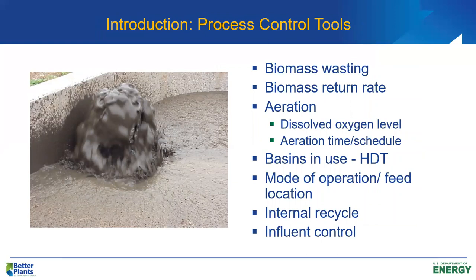In terms of process control tools, our primary tools are the biomass wasting rate (WAS) and the biomass return rate (RAS). Aeration is another key tool — how much aeration we're providing in the basin. The aeration system usually accounts for about 50% to 60% of our overall energy use, so we want to use it wisely to minimize operating and energy costs. There are times when we want to turn off our aerators for a few hours, which typically saves energy and also allows us to denitrify under certain conditions. We also need to know the hydraulic detention time (HDT) of our basins, which requires knowing the volumes of all our tanks.